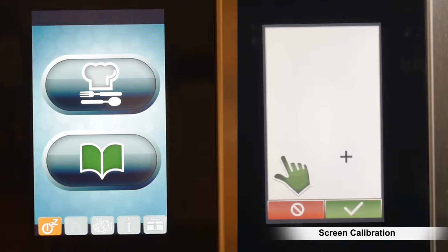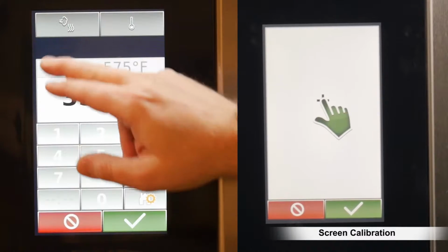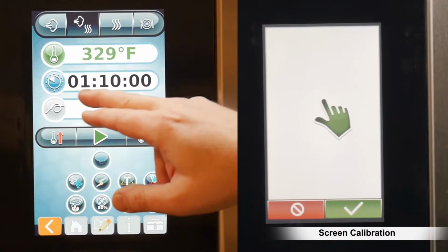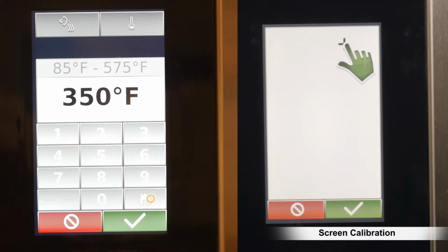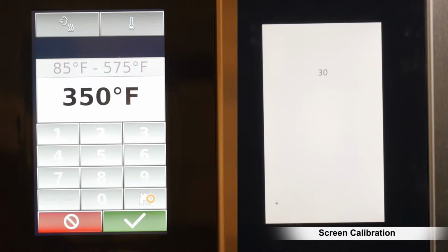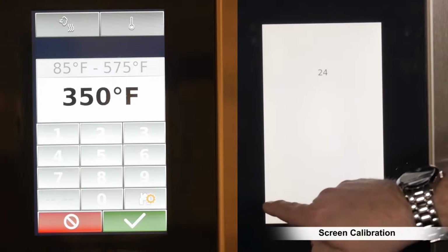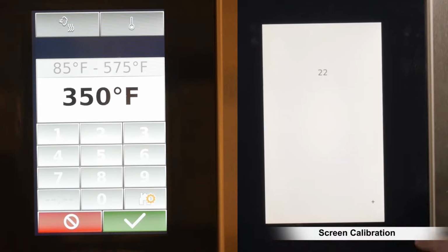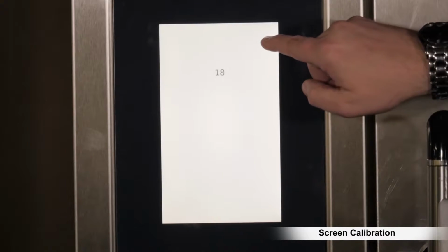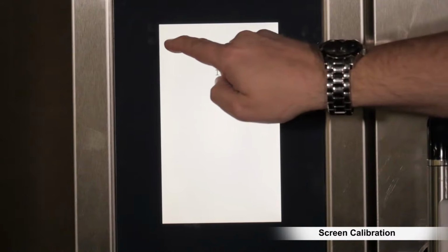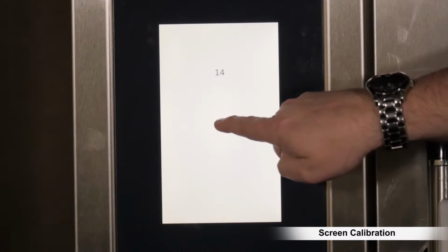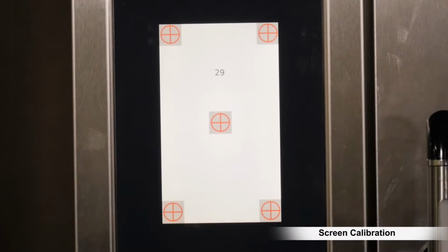Once we're into the calibration process, the oven is going to give me 5 points to touch on the screen to recalibrate the screen and allow me to operate the unit. As you see here on the countdown screen, it's giving me 30 seconds to do that. So down here on the bottom left, you see there's a plus. Here there's another plus. Every time I successfully touch each one, it moves to another corner of the screen. And then finishing right here, number 5 is in the center.